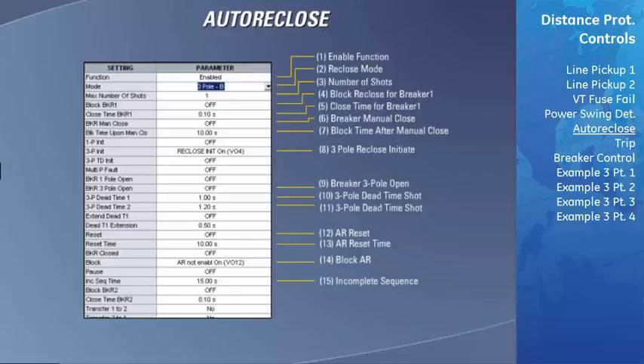Select a flex logic signal or input that will initiate 3-pole reclosing. Here, virtual output 4 was selected. The breaker 3-pole open field is used to indicate the status of the breaker. Enter the flex logic signal or input that indicates the breaker status. Select the dead time from when a breaker open condition is sensed until the first reclose command is issued. Here it is selected as 1 second.